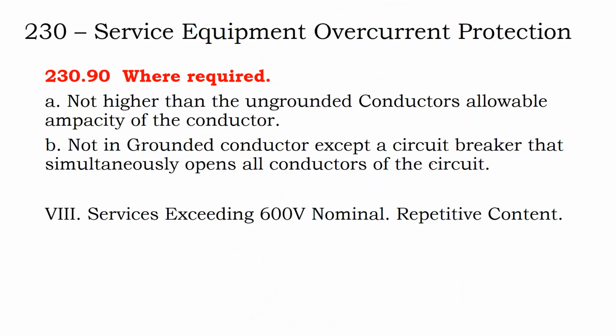Well, all that happened was we got up on the rooftop, swapped it out with a 15 amp fuse instead of a 10 amp fuse, and the system went along and worked its merry way. It wasn't like the installer had inserted a safety hazard into the system. It was just a slightly undersized fuse. And that was good. The system had a wrong component designed into it, and because it was a fuse rather than a breaker, it required someone to come out and actually diagnose the problem rather than just reset the problem.